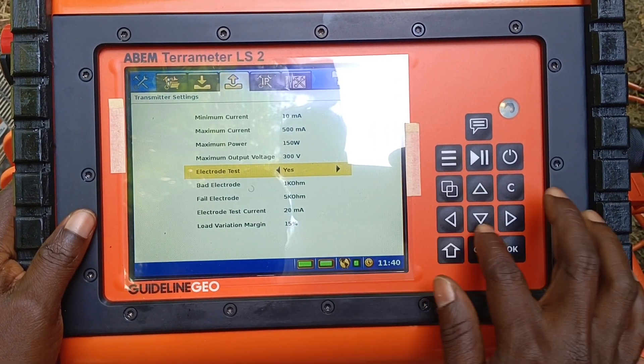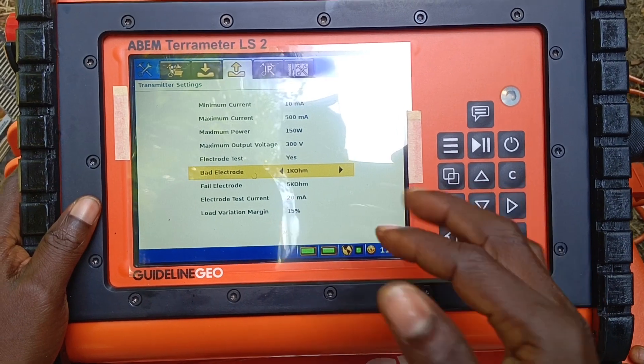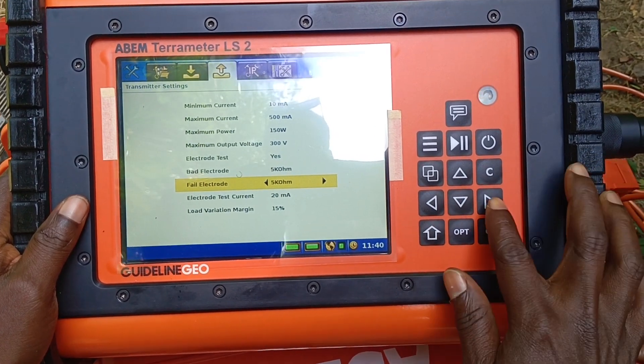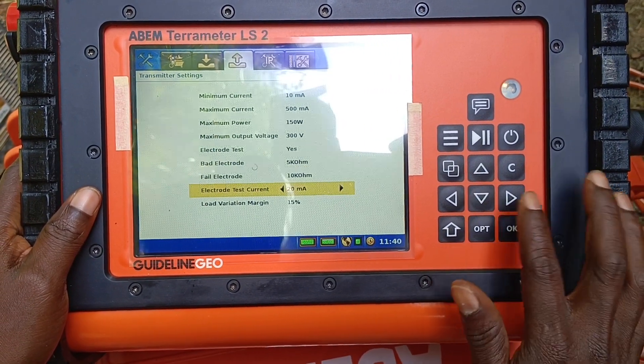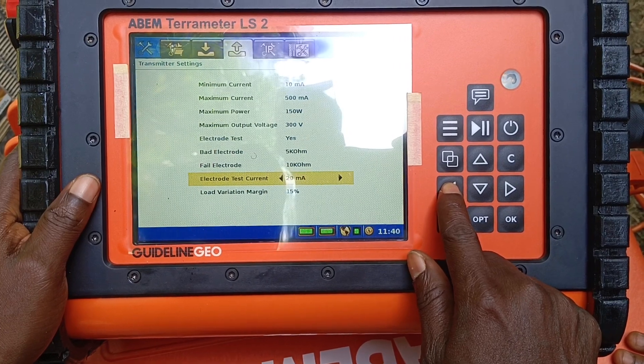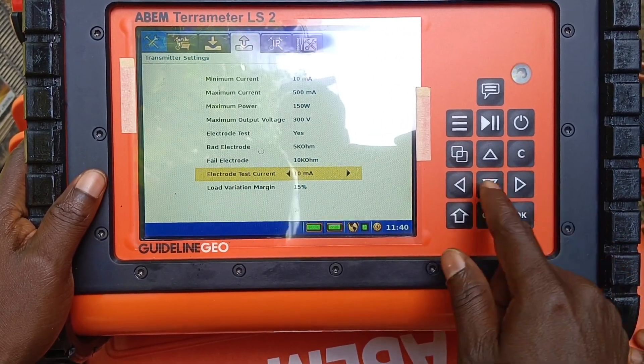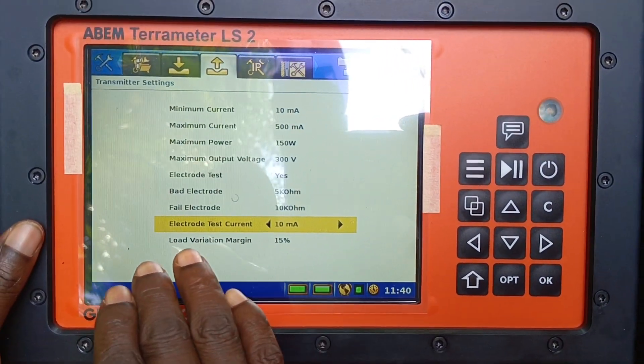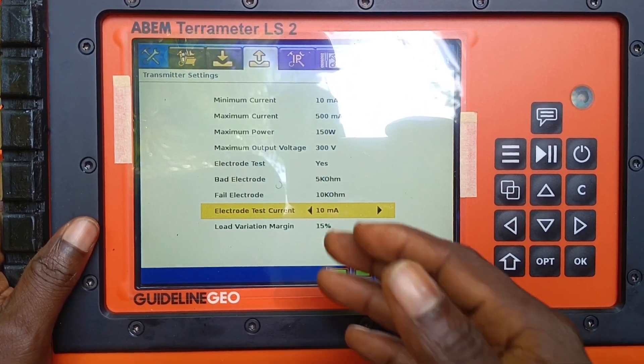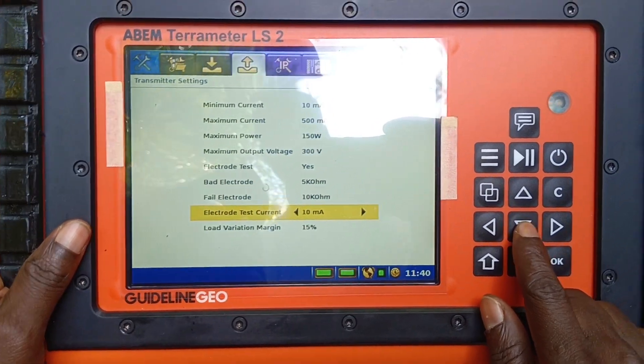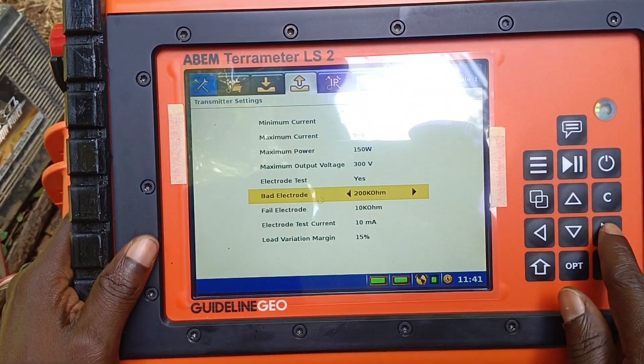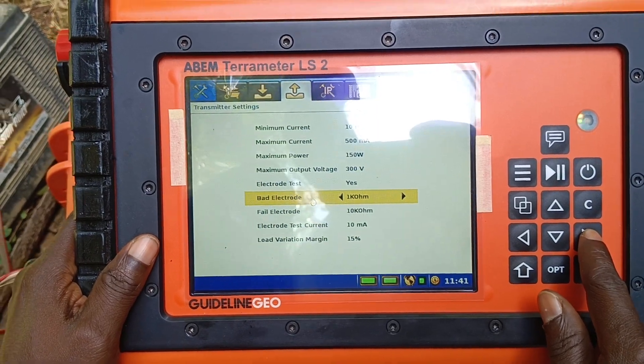Bad electrode — what's the minimum requirement to say the electrode is bad? We can set it at five. For an electrode to have failed, it should be like 10 kilohms. What's the minimum current to use for the electrode test? Maybe 10 milliampere. If 10 milliampere is able to go across and finds good contact with the ground, it will pass; if not, some will fail. What's the maximum value to determine whether the electrode is bad?